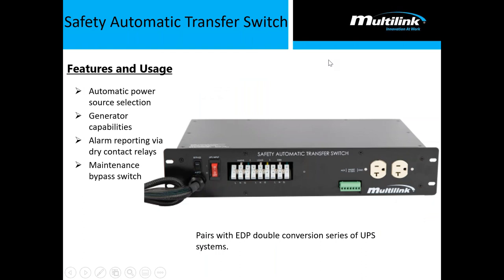The safety automatic transfer switch toggles between utility power, load power, and generator power — providing automatic power source selection. If there's a utility outage, the UPS switches to inverter mode, and once the battery string is empty, it automatically switches to generator mode while charging those batteries. Once batteries are charged, it shuts off the generator and pulls power from the battery. It's basically a brain you install into the cabinet so you don't have to manually select the power source or closely monitor where your equipment gets its power from.